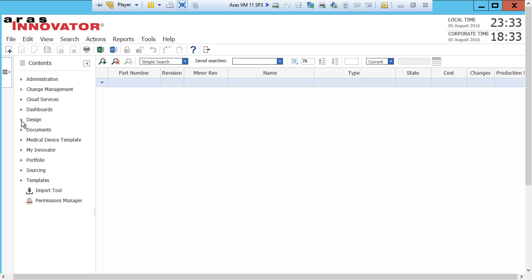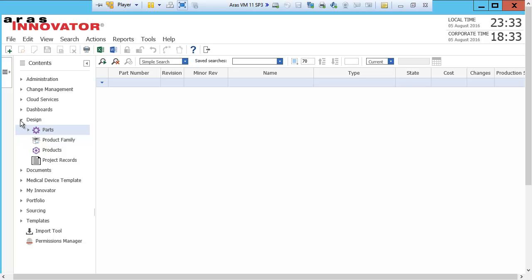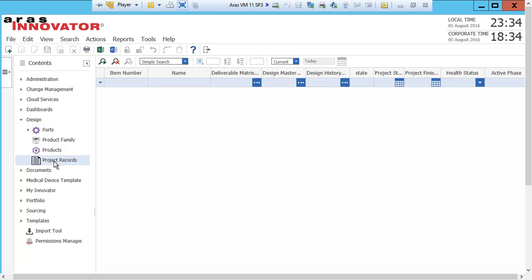After logging into innovator, I navigate to the design menu section. Here you will see a menu selection called project records. If you remember from our other presentation on Minerva's medical device PLM, design history files, device master records, and deliverable templates are created and then instantiated in a project. I see that I have three projects instantiated, one of which is off-track.